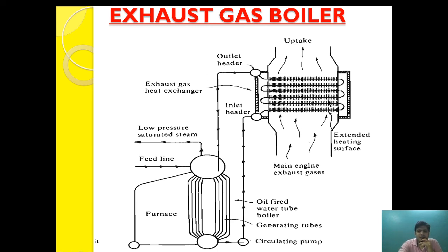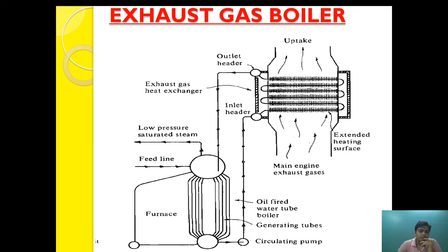To enhance heat transfer in the exhaust gas boiler, tubes are provided with mild steel fins. The staggered fins divert the exhaust gas coming from the main engine, giving more contact time for the heat exchange process and improving efficiency. However, if the exhaust gas contains sulfur and other impurities and the temperature falls to around 170 to 180 degrees Celsius, the sulfur will settle on the tubes and cause corrosion.